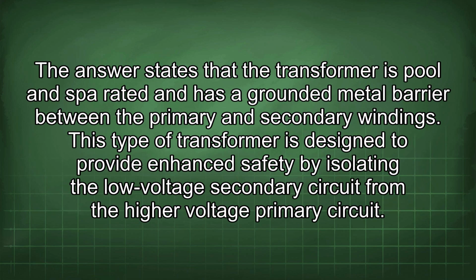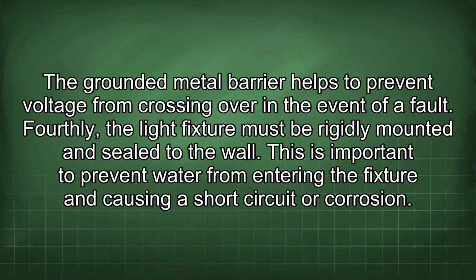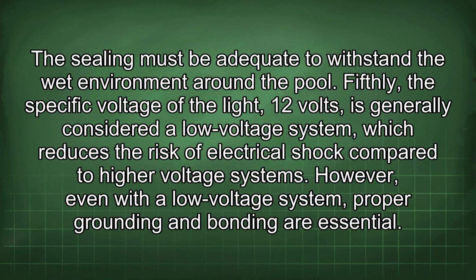The answer states that the transformer is pool and spa rated and has a grounded metal barrier between the primary and secondary windings. This type of transformer is designed to provide enhanced safety by isolating the low voltage secondary circuit from the higher voltage primary circuit. The grounded metal barrier helps to prevent voltage from crossing over in the event of a fault. Fourthly, the light fixture must be rigidly mounted and sealed to the wall. This is important to prevent water from entering the fixture and causing a short circuit or corrosion. The sealing must be adequate to withstand the wet environment around the pool.